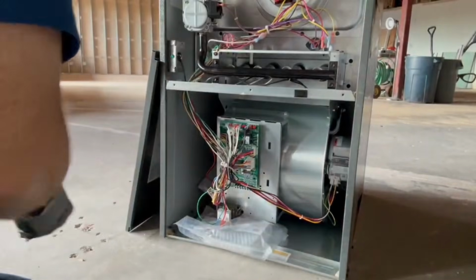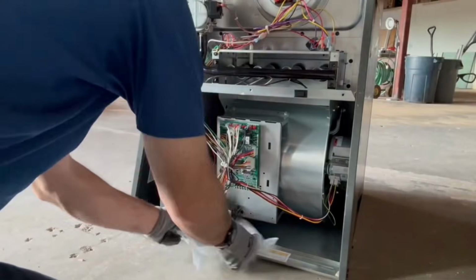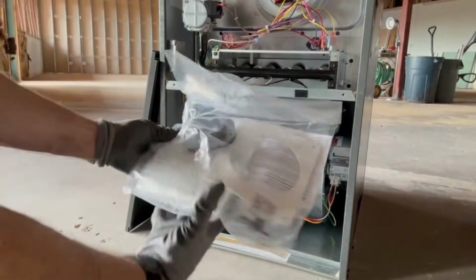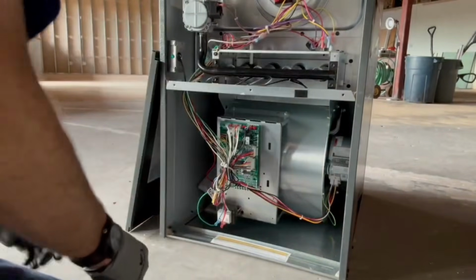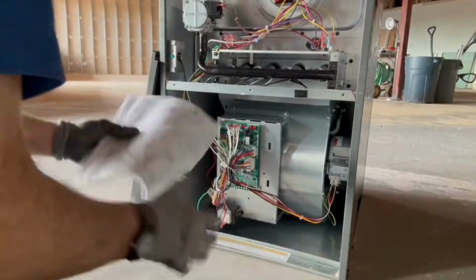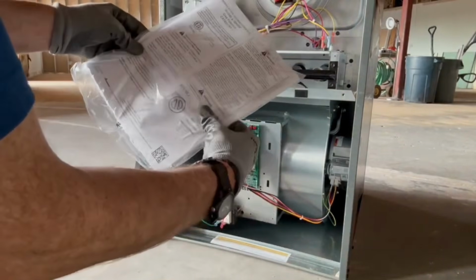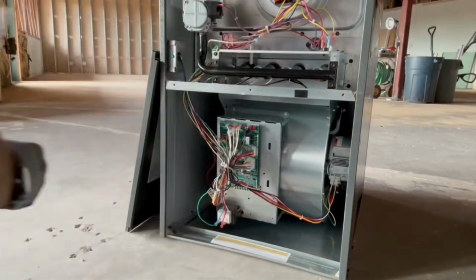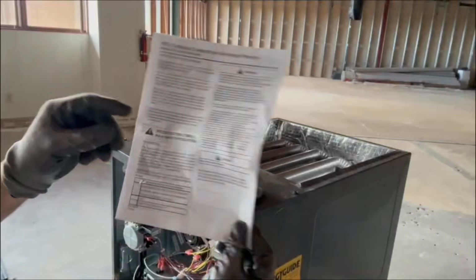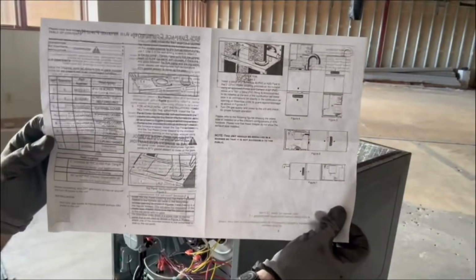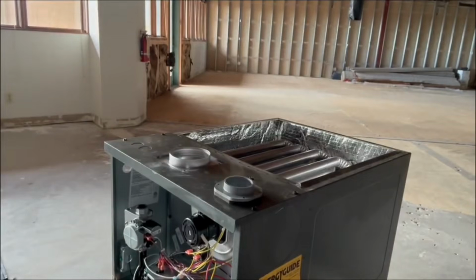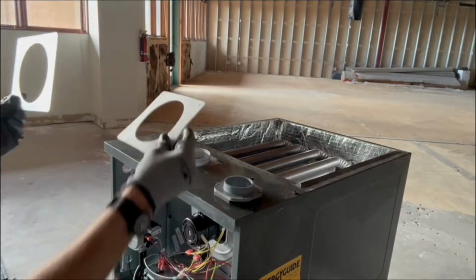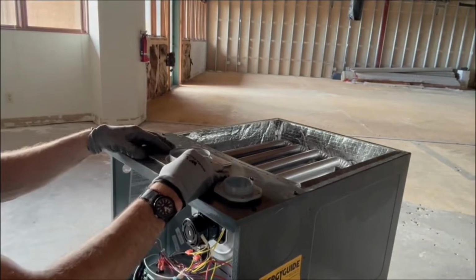There's our wiring schematic. Here's our ignition control board. Here's our owner's manual. This is one of those ECM blower motors, multi-speed motor. Literature. So the instructions, like I was saying, because it's A2L, I need to install a PVC fresh air intake and also this gasket and this metal plate because they want everything sealed.